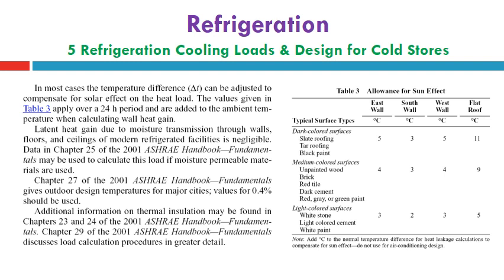Additional information on thermal insulation may be found in chapters 23 and 24 of the 2001 ASHRAE Handbook Fundamentals. Chapter 29 of the 2001 ASHRAE Handbook Fundamentals also discusses the load calculation procedure in greater detail. On the right side of this slide, we can find table 3, which indicates the allowance for sun effect for east wall, west wall, south wall, and flat roof. The typical surface types are grouped into 3 types: dark colored surface, medium colored surface, and finally light colored surface.